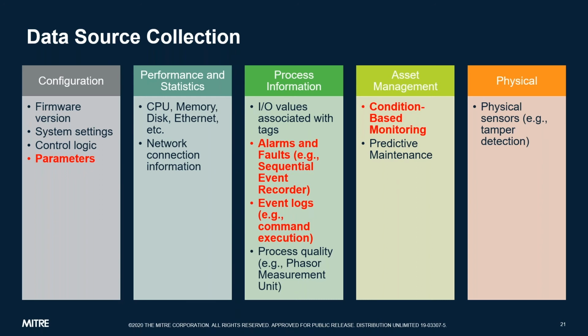So for instance, we could always pull the parameters that have been assigned to a controller off the controller. We could also understand when these change if particular controllers log these events. Also, alarms and faults are usually recorded somewhere. So if we are looking at those, we can get a good idea of when some of these activities have occurred. So there's a lot more data in these environments than just the network based data sources. And we would encourage you to understand what's available on the host as well.